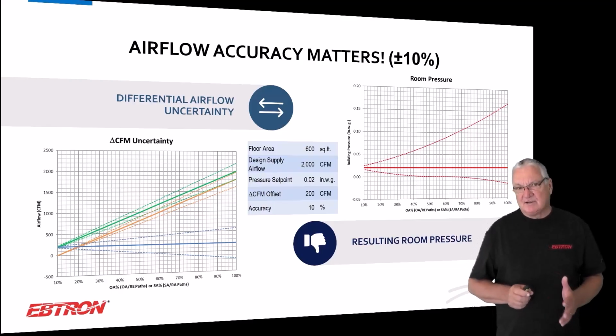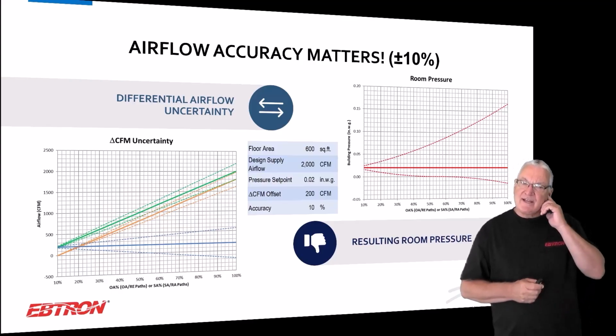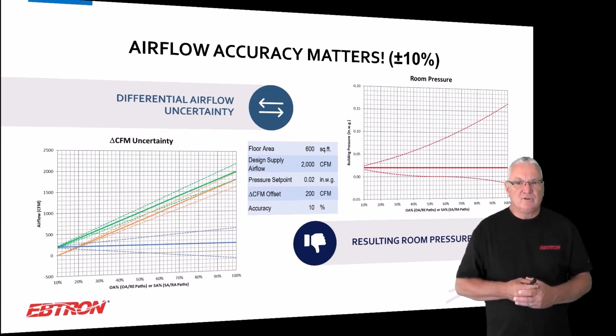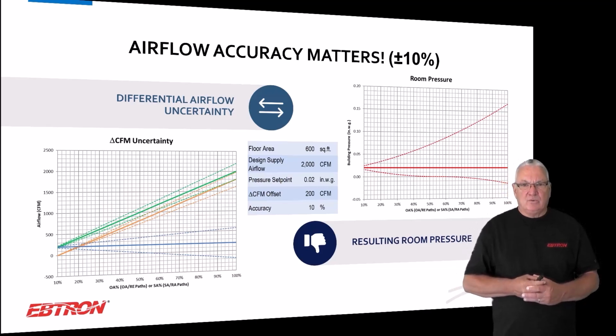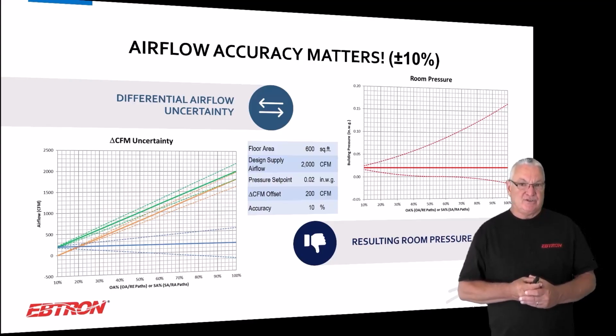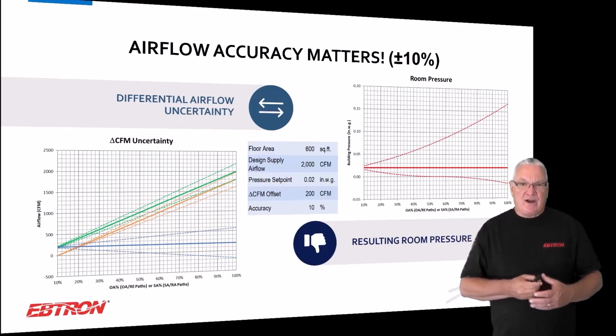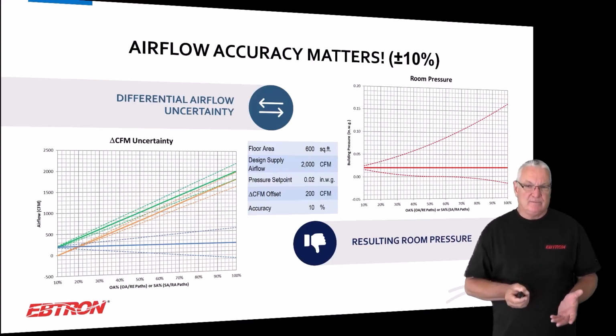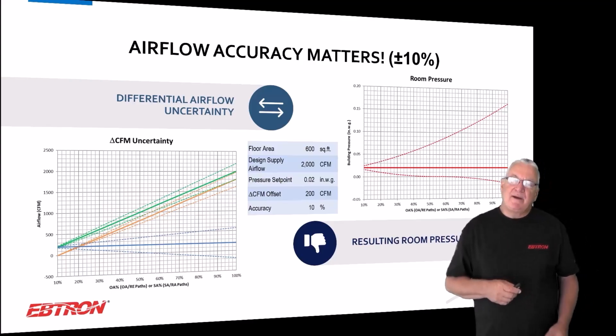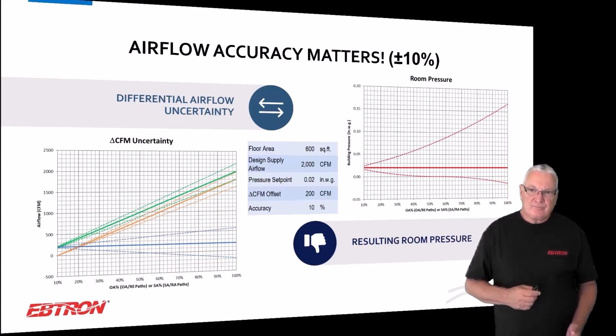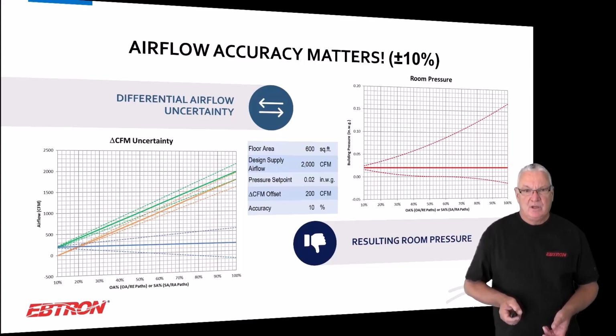It's not necessarily that because things change, but let's just go with that for a second. So I calculate a flow coefficient for that room. And so, when you look at that right-hand graph, which is what the actual room pressure is, you'll find that red solid line is what your target was, and the dashed reds are where you could be, and it's all over the place. And what ends up happening, I think, is that you go in and you balance these spaces until you get the pressure where you want them, okay?